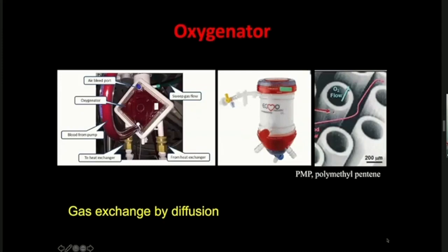The membrane oxygenator is the artificial lung of the ECMO circuit. It comes in different shapes, sizes, and configurations — for example, the Quadrox membrane oxygenator has a squarish setup, while the ERS system is a cylindrical column. Most modern oxygenators are made of polymethylpentene, with hollow fibre structures. Blood flows between the fibres and gas flows within the hollow fibres, providing a large surface area for contact, so oxygen and gas exchange occurs very rapidly by diffusion down the concentration gradient.